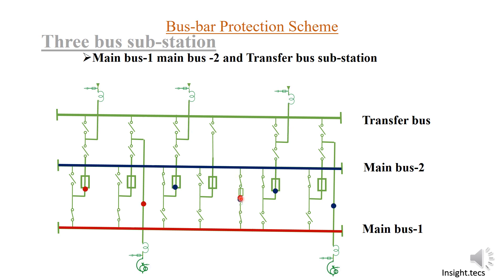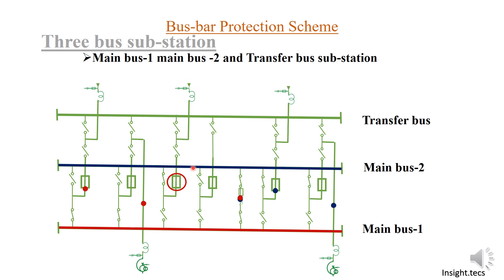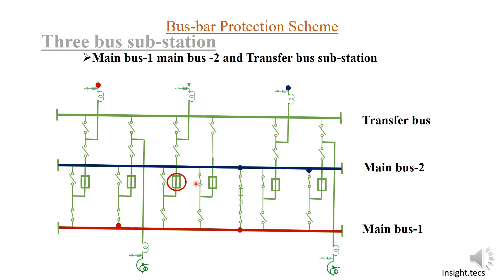Sometimes there can be a problem with a circuit breaker — say you want a circuit breaker to go under maintenance for a few days. This is the main feeder charging the bus, but if there is a problem in this circuit breaker, then this feeder will not charge the bus. In that case we use the transfer bus. We close the relevant isolator, turn off Bus 2 selection, and close the transfer bus isolator.